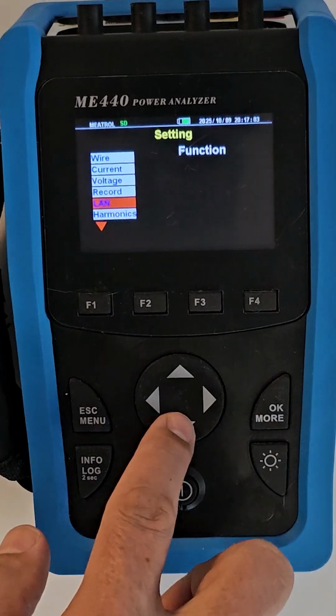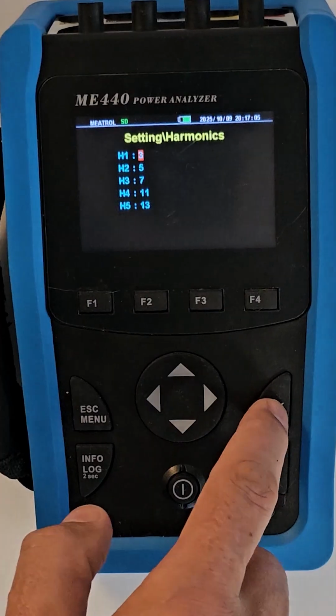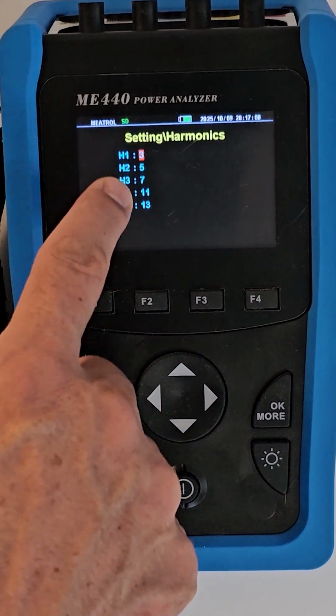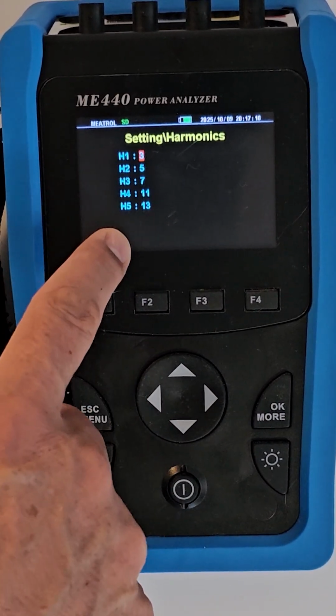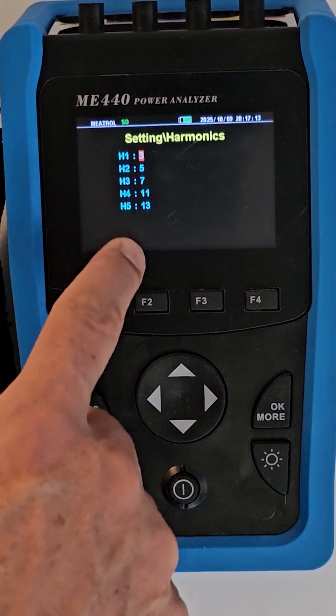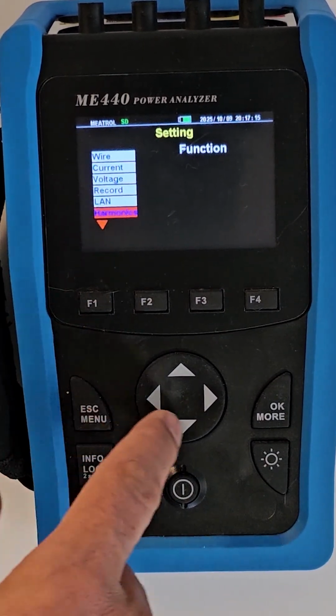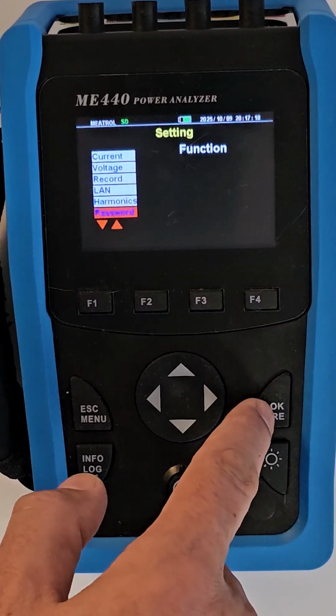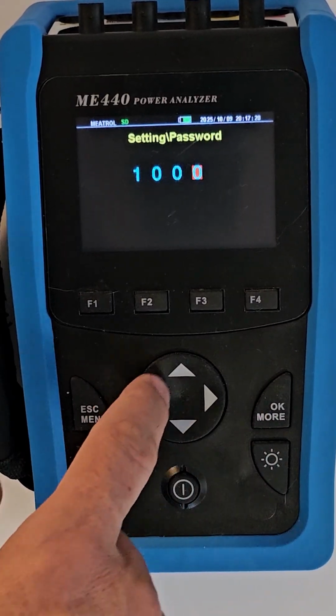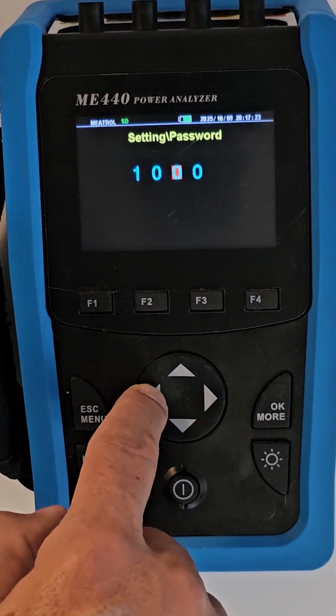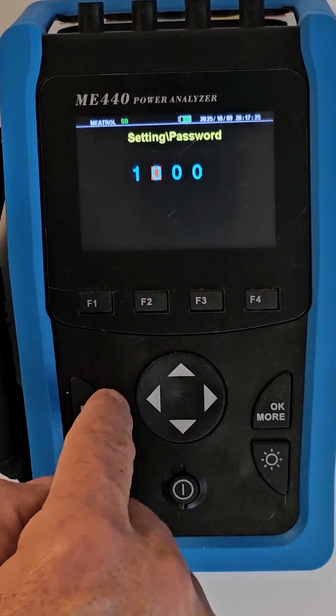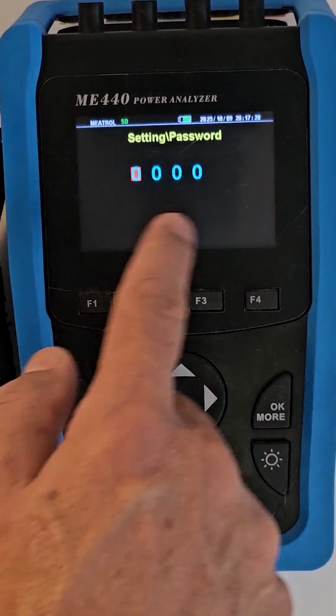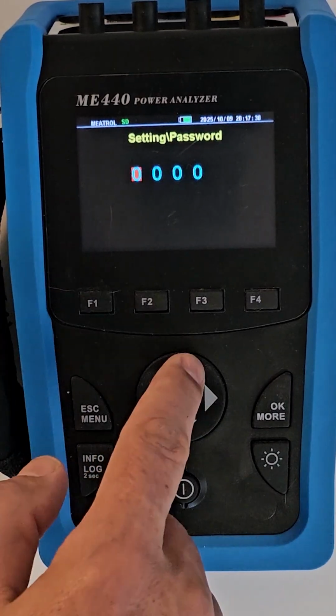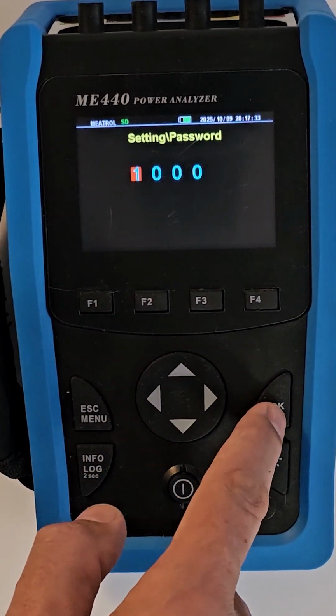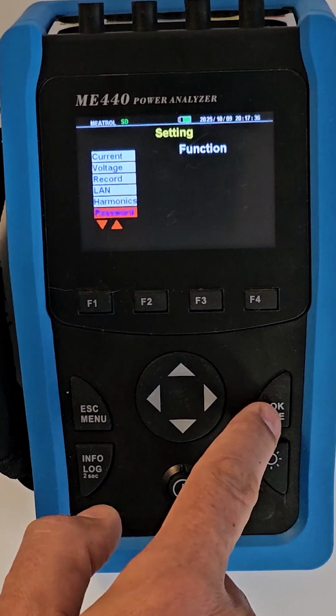Okay, so if we go into the harmonic screen, you can just set which harmonics it records, up to 5 different ones. Okay, and here you can set the password. Default password is 1000, so you can just move to the left or right and change the password. If you set it to 00, it's disabled. So let's just leave it at the default of 1000 and press OK.